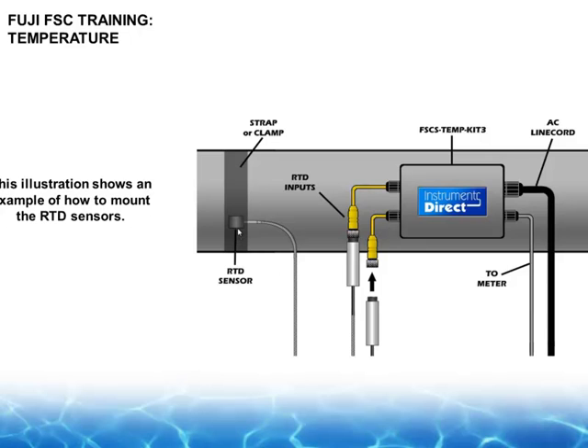So this is different than a wetted sensor. The key here is we're looking for our equation, the temperature differential. So if you were to put this sensor on the supply line at 3 o'clock and then put another one on the return line at 3 o'clock, you're going to have the data that you need. And this is important too.